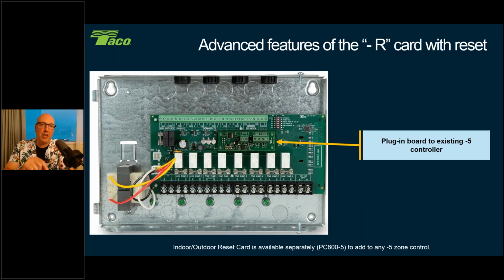You plug in a PC 700, 702, or 705 into that spot there, you're going to let the smoke out of both controls. But yes, you can tie in the PC 705, and yes, the PC 700 is still available today. We have not discontinued any of that, even though the PC 800 does replace the PC 700 if you had an existing. And you know what, the 800 is not a very expensive item to add to this board. So me personally, if you had a system that had a dash 4 with the PC 700 and the magic smoke was let out of the dash 4 board, I'd probably replace both rather than keeping something else that was already connected to something that let the smoke out. But yes, we still have them available today.